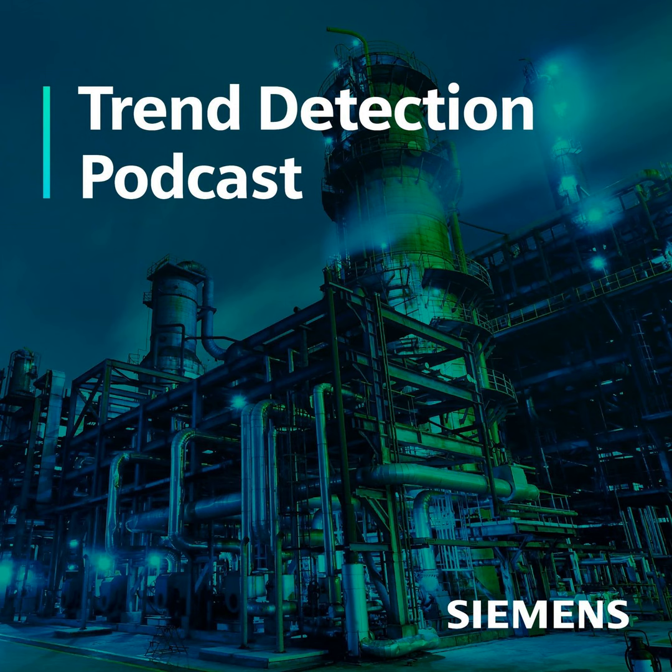It shows some of that fine tuning that we can do once we have an understanding of the system and the assets, and combine those. Exactly, and I remember you showing me the graph: here's the before and we're not detecting here and here, and then here's the after, and we're not detecting on these peaks that were normal, but we are detecting on this peak that we then had an issue off the back of. So there is that ability to turn some dials and really fine tune on even slight changes in the way your data's moving when there's an issue, as opposed to when there's just a nominal interaction with the machine.